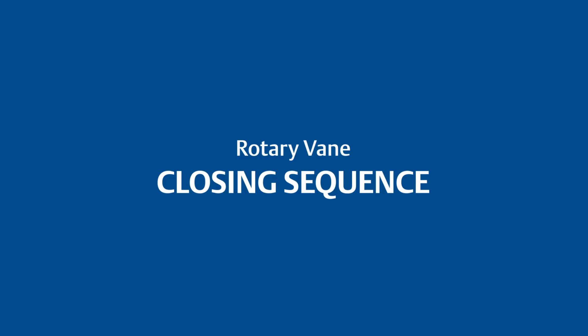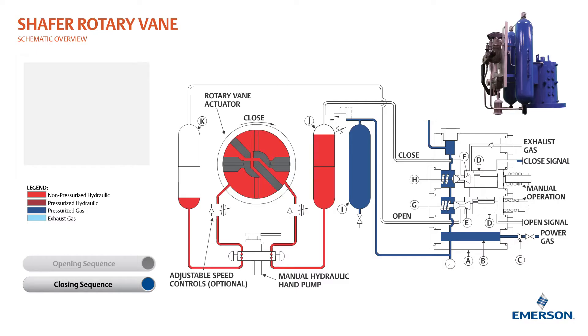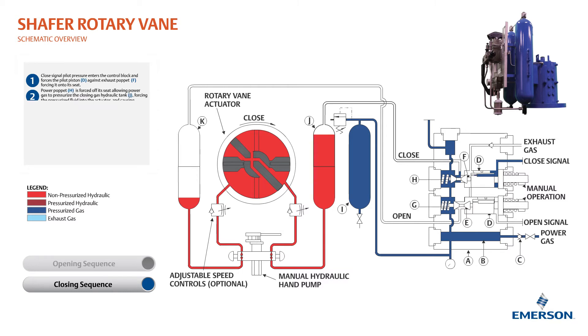This is the theory of operation for the closing stroke for the Shafer rotary vane actuator. Closed signal pilot pressure enters the control block and forces the pilot piston against the exhaust poppet, forcing it onto its seat. The power poppet is then forced off of its seat.